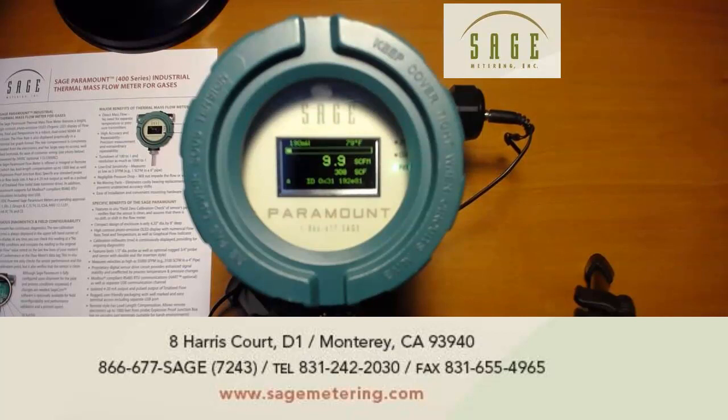The Paramount has our latest microprocessor technology. In addition, we provide a very bright, organic LED display. You can see the flow rate, totalized flow, temperature, and even a horizontal bar with a percentage of full scale. On the top left, the smaller numbers is a diagnostic. That is the raw calibration of the meter, and is also used for the popular in situ calibration procedure.